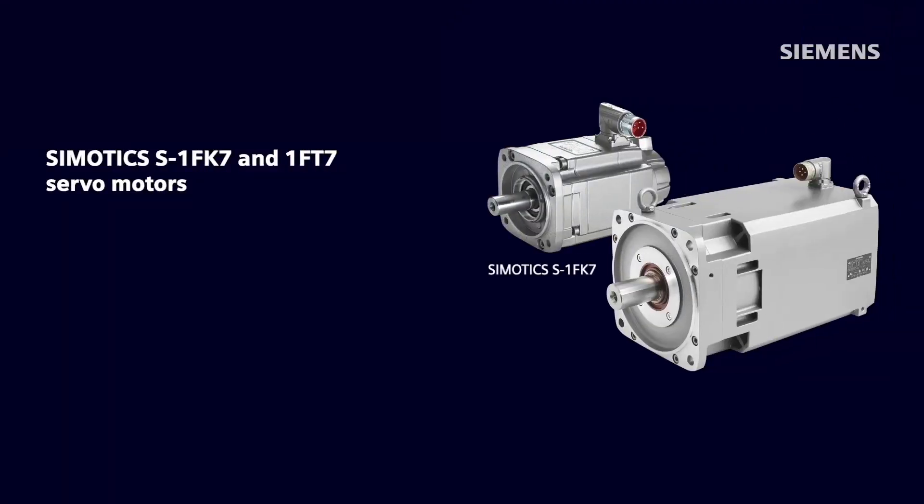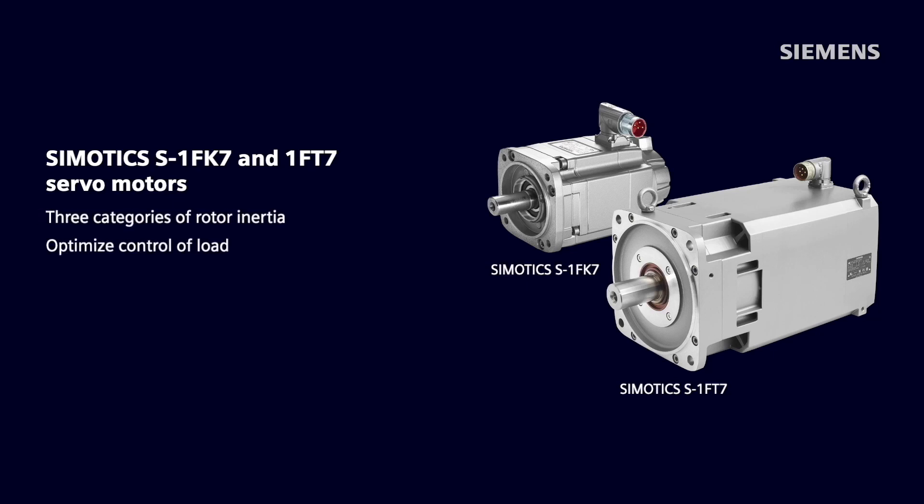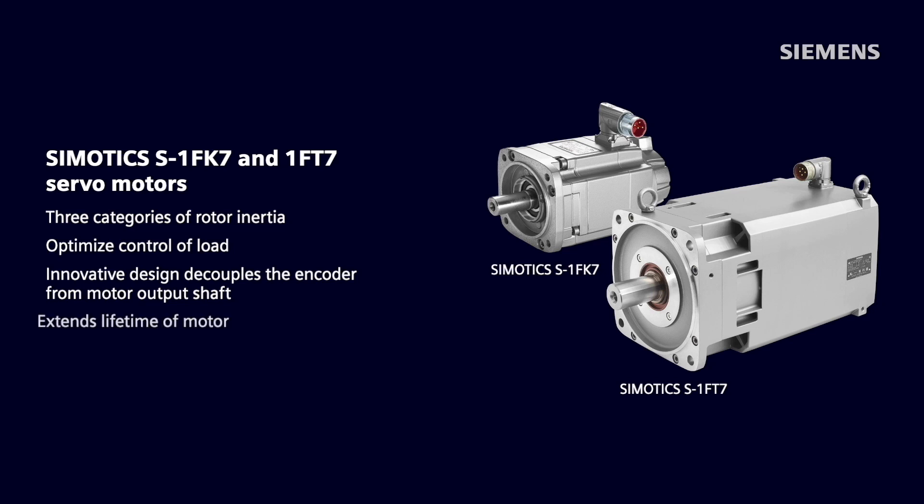SIMOTICS S 1FK7 and 1FT7 servo motors include three categories of rotor inertia to help customers optimize control of load. Their innovative design thermally and mechanically decouples the encoder from the motor output shaft, which extends the lifetime of the motor since the encoder is exposed to less thermal and vibration stress.